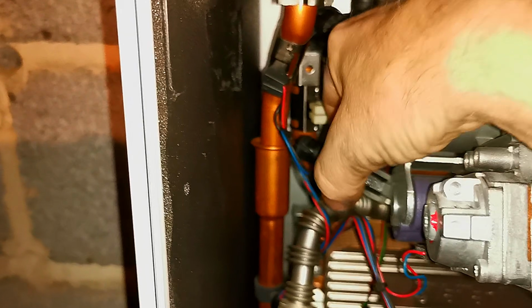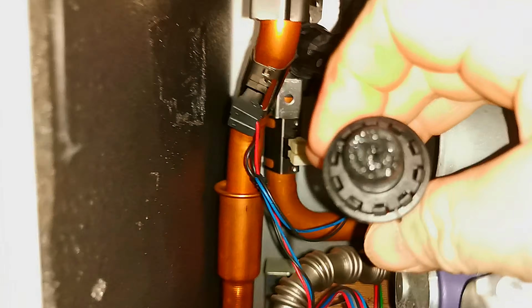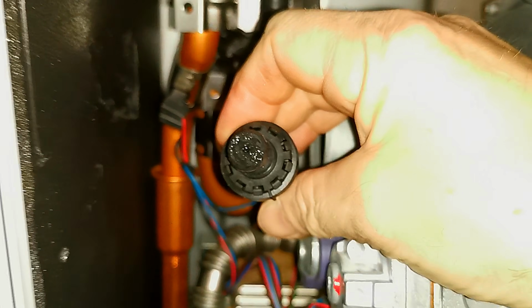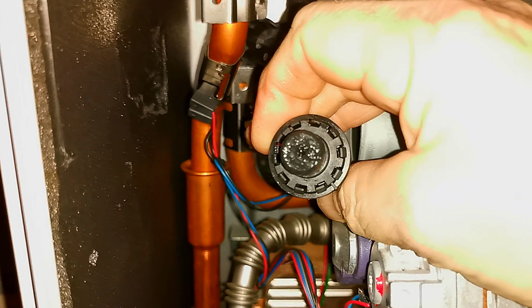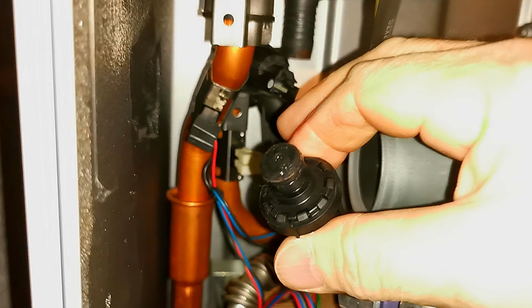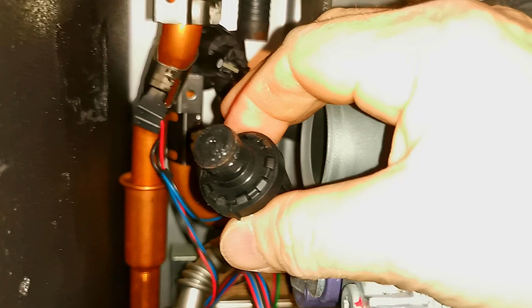If we take a look at this pressure sensor, which I've just removed from this boiler, you can see that the end of it is all blocked up with magnetite. That's why the pressure sensor was overreading and they were getting F75 coming up on their display.